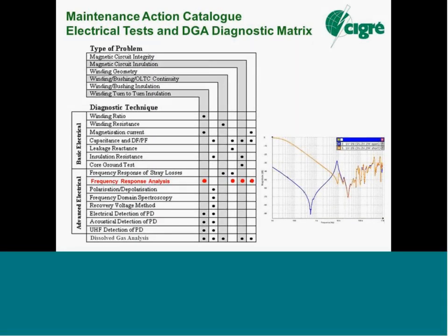We take electrical tests and DGA as our important diagnostics when we are concerned that there is something wrong with the transformer, especially if the transformer has produced an alarm or has just tripped. We check the protection, decide that it is a genuine problem in the transformer, and it's useful to consider this diagram here to show what the various basic and advanced electrical tests are that can be done, together with dissolved gas analysis on the bottom row of the diagram. What do they tell us about the transformer? What types of problems are these tests useful for detecting?